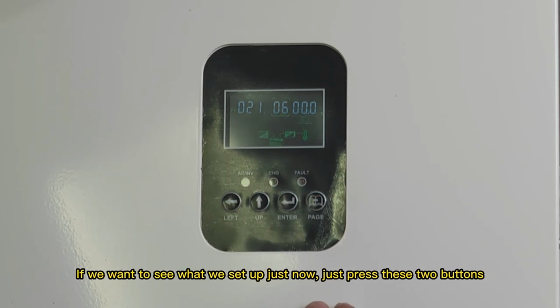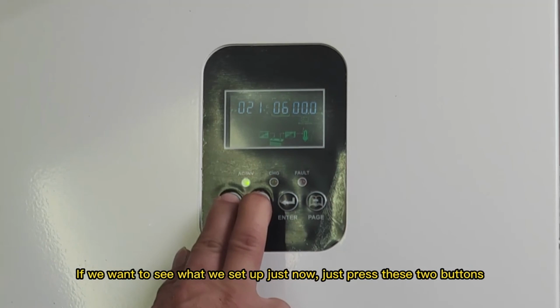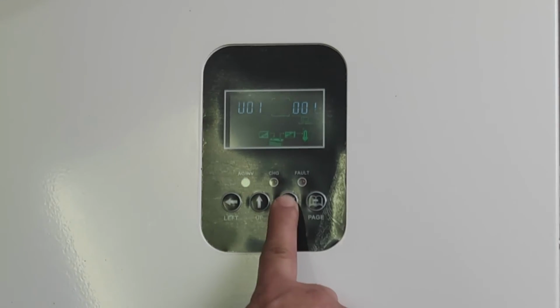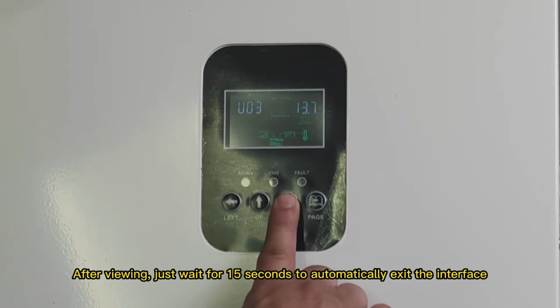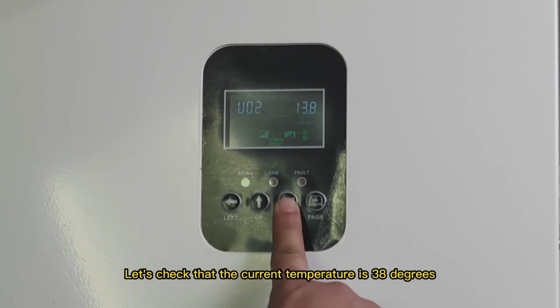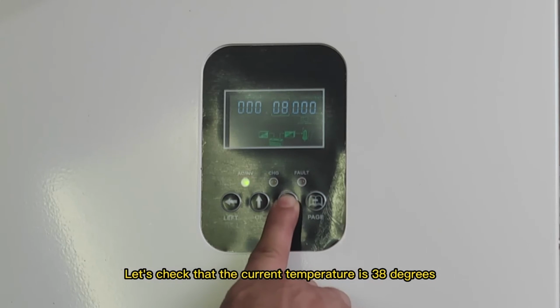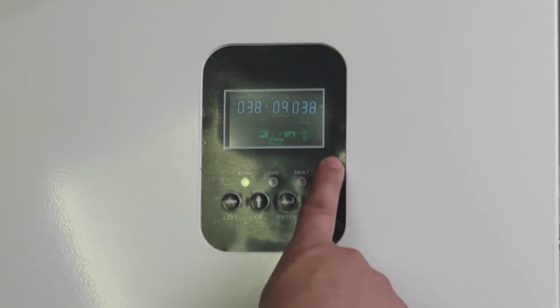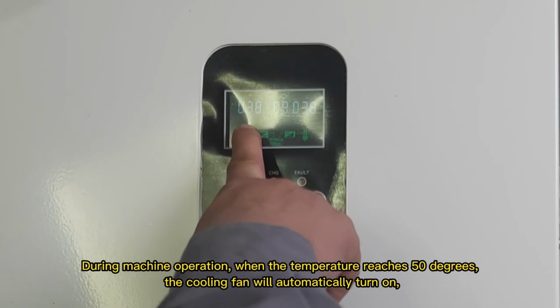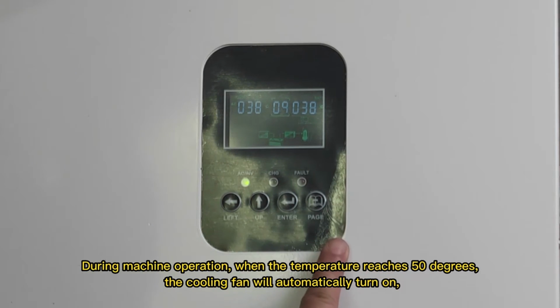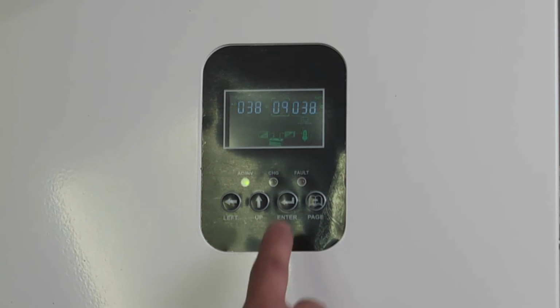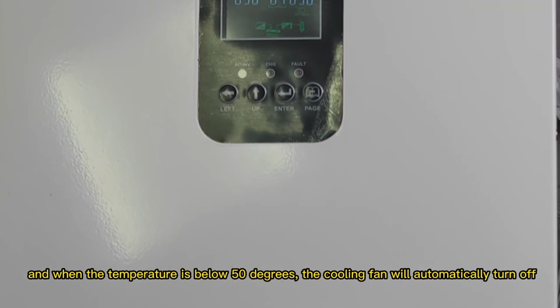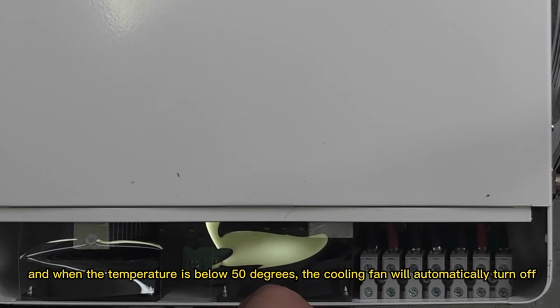If we want to see what we set up just now, just press these two buttons. After viewing, just wait for 15 seconds to automatically exit the interface. Let's check that the current temperature is 38 degrees. During machine operation, when the temperature reaches 50 degrees, the cooling fan will automatically turn on. And when the temperature is below 50 degrees, the cooling fan will automatically turn off.